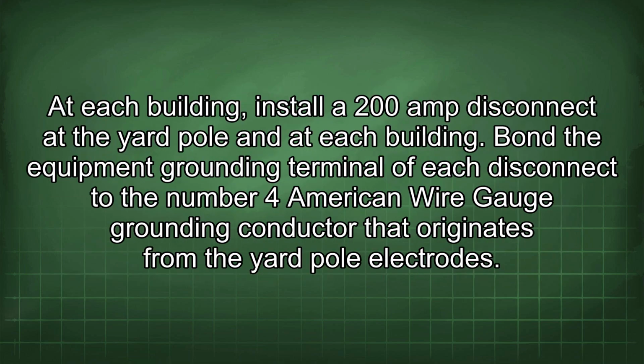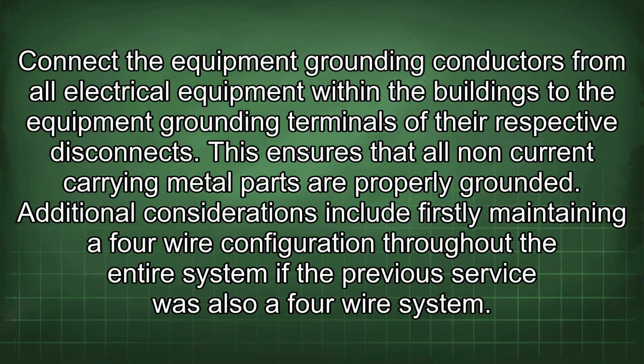At each building, install a 200 amp disconnect at the yard pole and at each building. Bond the equipment grounding terminal of each disconnect to the number 4 American wire gauge grounding conductor that originates from the yard pole electrodes. Connect the equipment grounding conductors from all electrical equipment within the buildings to the equipment grounding terminals of their respective disconnects. This ensures that all non-current carrying metal parts are properly grounded.